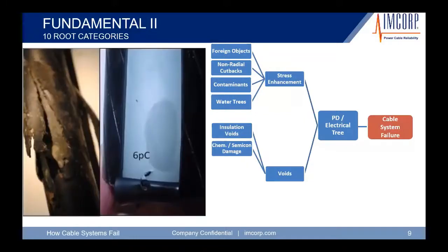Contamination. So hydrocarbons and carbon black of the semicon do not mix. So this particular one not only had a cut in the semicon, but it was contaminated with oil. Typically we see this near transformers or where cables may be lying in some sort of hydrocarbon oil type. This will contaminate it. When the hydrocarbon gets to the carbon black, it actually separates the carbon black in that semicon material, causing a more resistive, insulative type material. And then here you see the picture on the left-hand side where it contaminated the cable and made it go to failure.